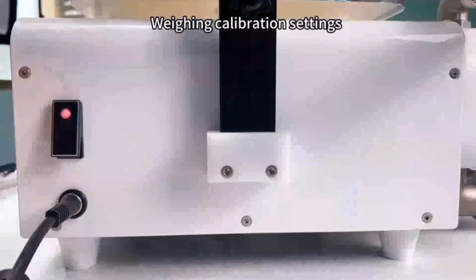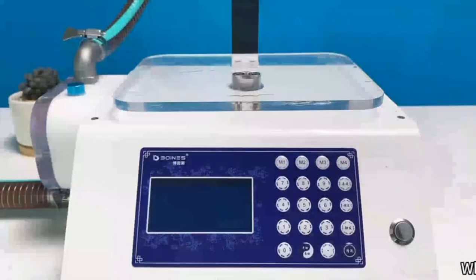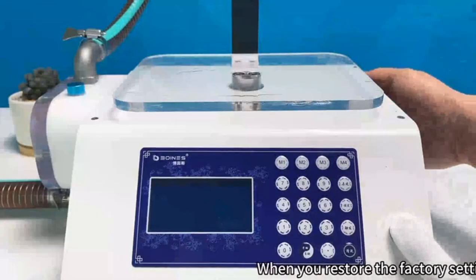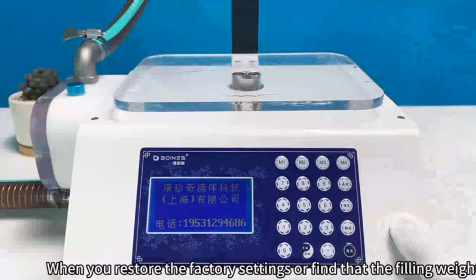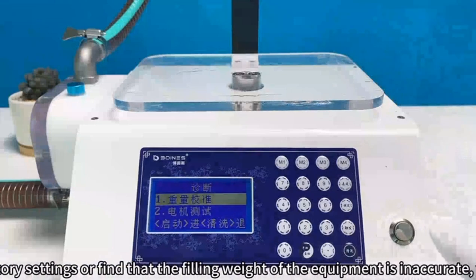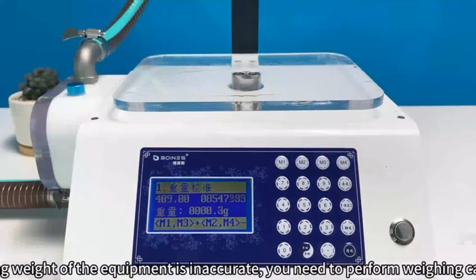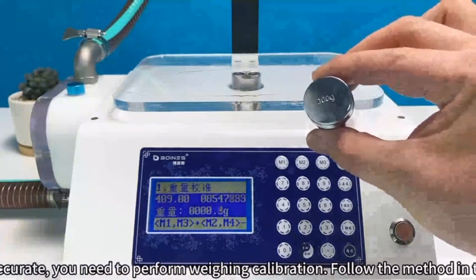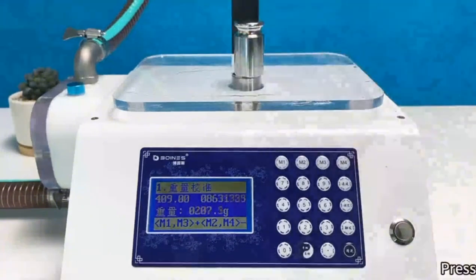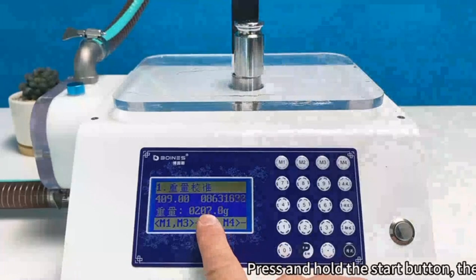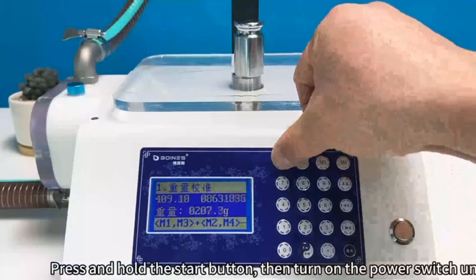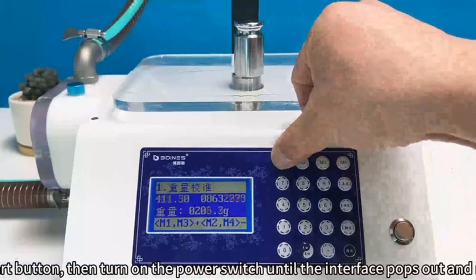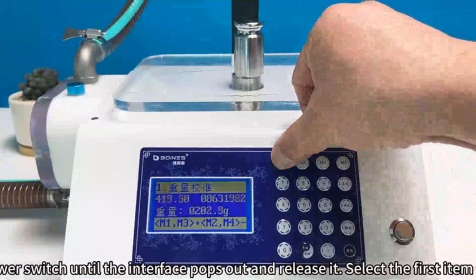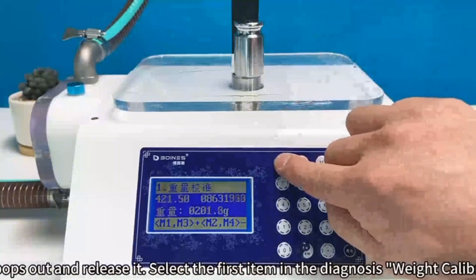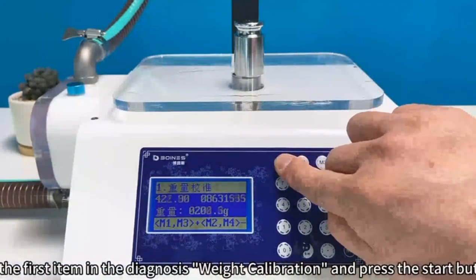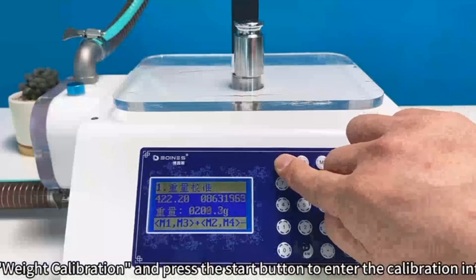Weighing calibration settings. When you restore the factory settings or find that the filling weight of the equipment is inaccurate, you need to perform weighing calibration. Follow the method in the video as follows. Press and hold the start button, then turn on the power switch until the interface pops out and release it. Select the first item, weight calibration, in the diagnosis menu and press the start button to enter the calibration interface.